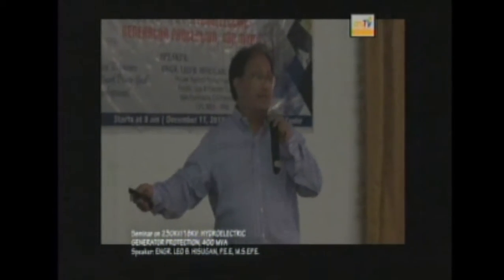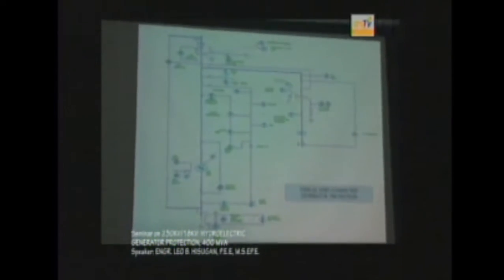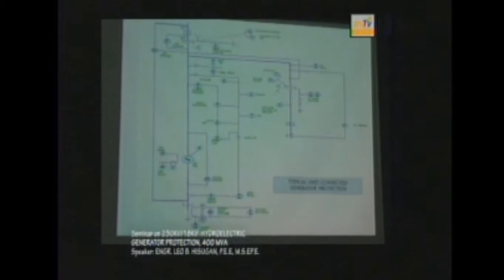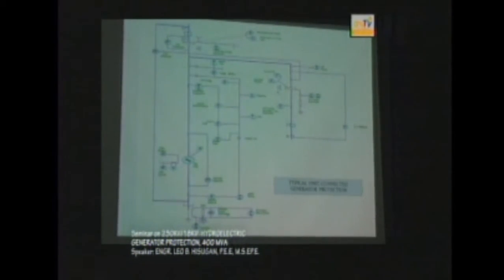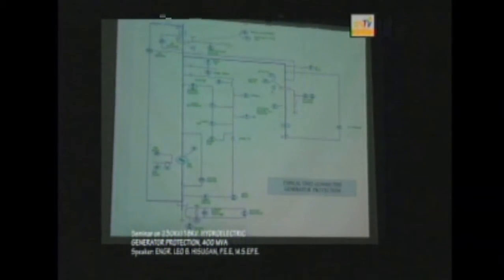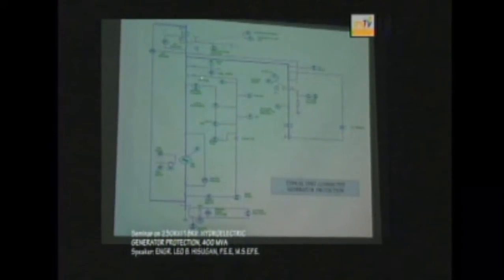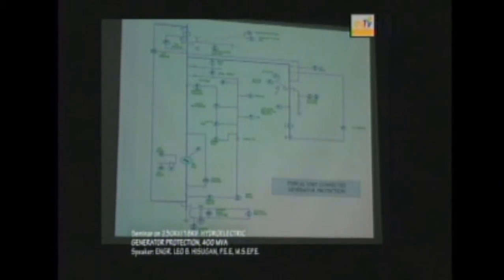We have the 59 device, which is your over voltage protection. For the 59 device, we set the over voltage protection like 120 to 130% of your voltage for your protection. The 27 device is your under voltage relay. We normally set those at 80% of your voltage, to your relay.